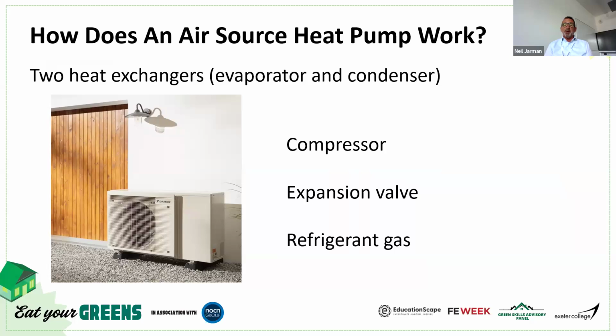So how does an air source heat pump work? Well, it has two heat exchangers, the evaporator and the condenser. If you look at the image there, in behind the grill you'll see there's a fan. The evaporator sits right in behind that fan. So basically the fan will draw the air over the evaporator, which is a little bit like a car radiator to a point, but with lots of refrigerant pipework within it. And then the condenser is the heat exchanger, where the heat transfer occurs.